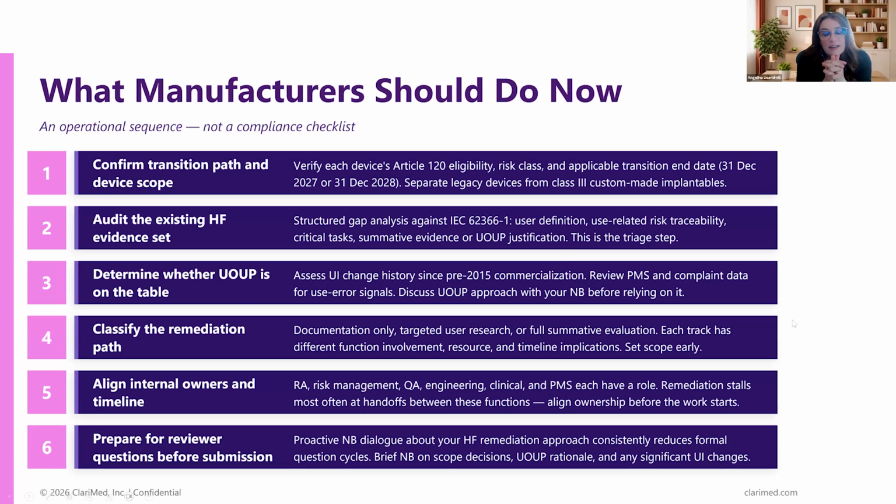That's great. I'll add on to that. For those that have done GSPRs under IVDR, you're going to have to justify your human factors in the GSPR. The first 9 GSPRs are identical between IVDR and MDR. If you don't have a justification for those, you're going to get that question asked. And so to the extent that you have to do it, it all depends on the device, typical reg response, but the higher class the device, the stronger the documentation, the stronger the testing you might need.